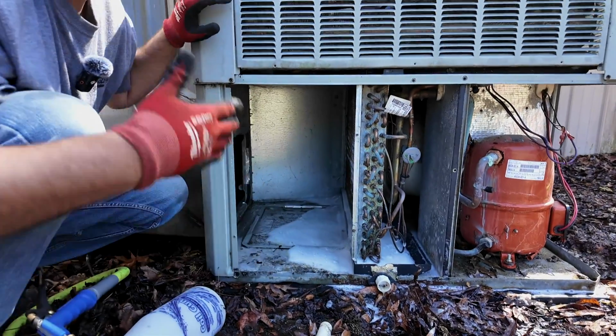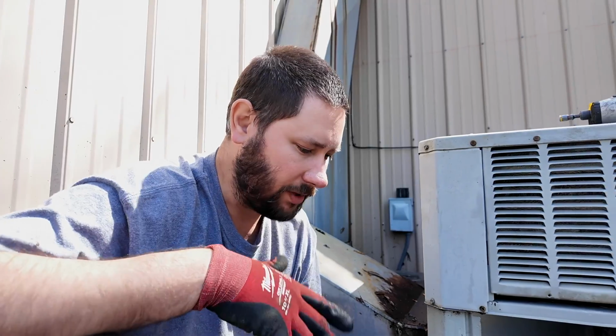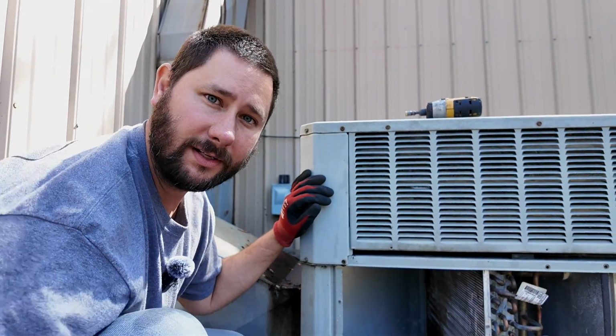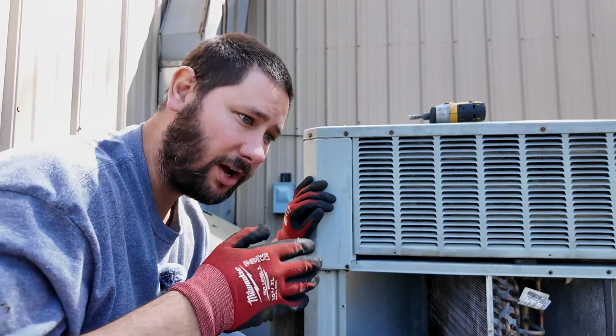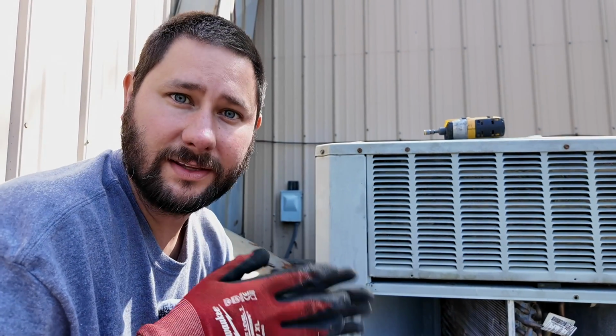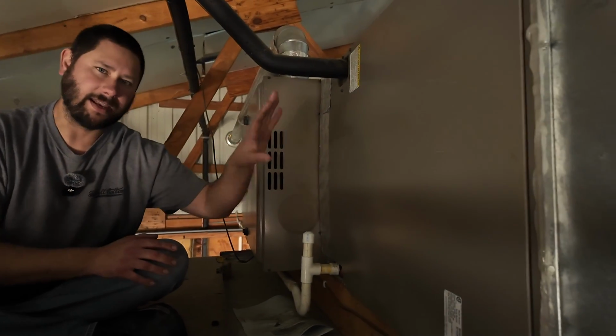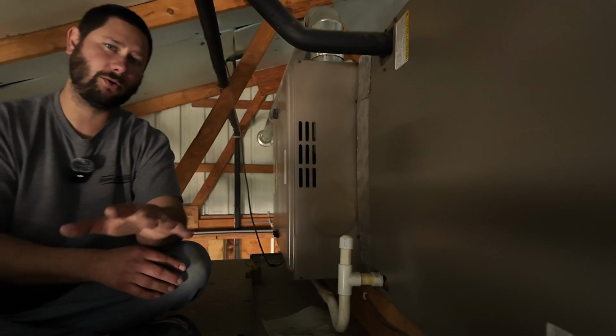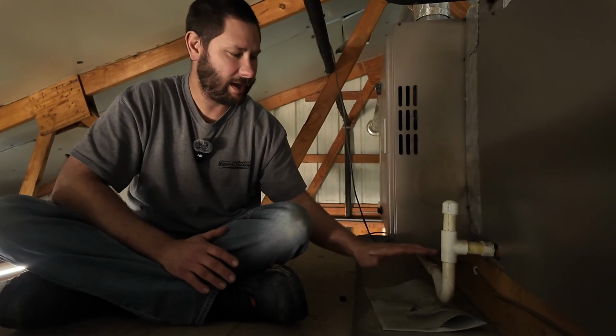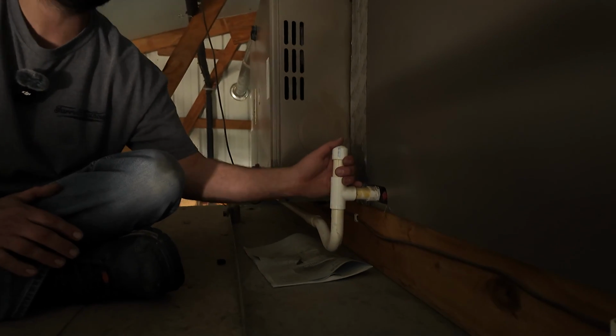If your water stays in your pan and you're not removing that moisture from your house, then it's going back into your house. This can cause humidity issues. So you want to make sure that you clean the trap. Now, I'm going to explain what can happen if you don't maintain a split unit that you're cleaning. We're upstairs in the attic area. This is a split unit. It has a gas furnace and an indoor coil. This coil is just like the coil in that packaged air conditioning system. The most important step for annual maintenance is making sure you clean out this trap. So clean out this drain.